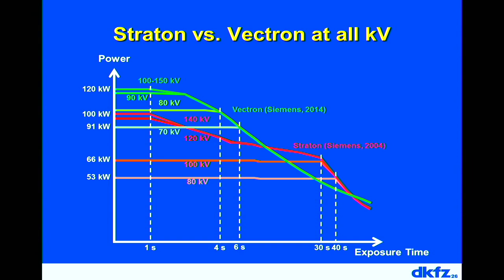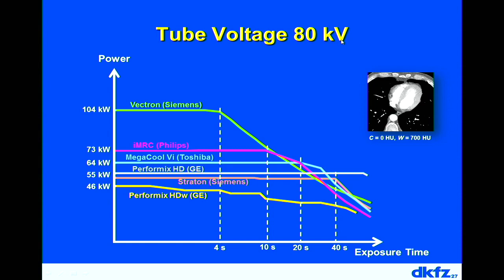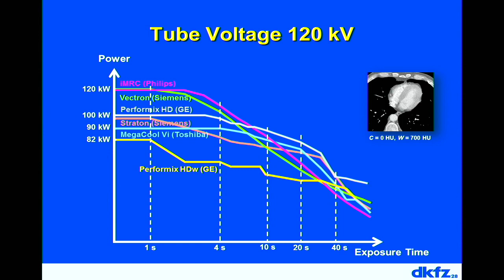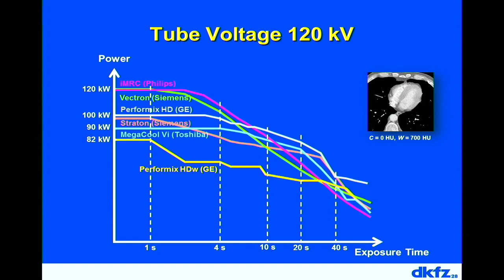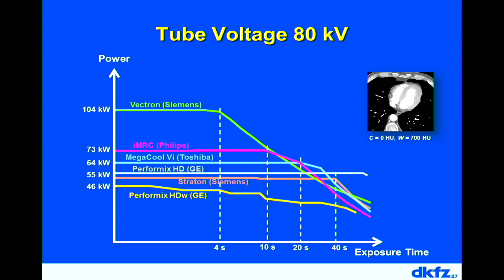Why do we need such high X-ray power? At low tube voltage — for example 80 kV — contrast agent in the heart produces better contrast than at high tube voltage. So we prefer low tube voltage scans for more contrast, which also reduces X-ray dose and the amount of contrast agent needed. With a pre-filter, low-energy photons are removed before reaching the patient; those photons would not make it through the patient anyway, so removing them reduces patient dose.